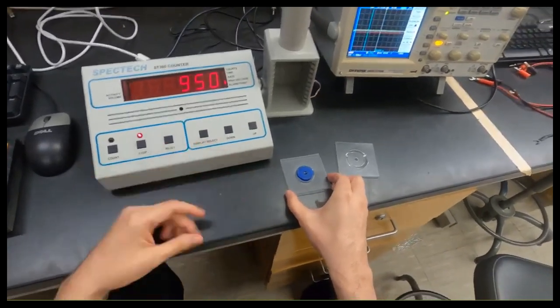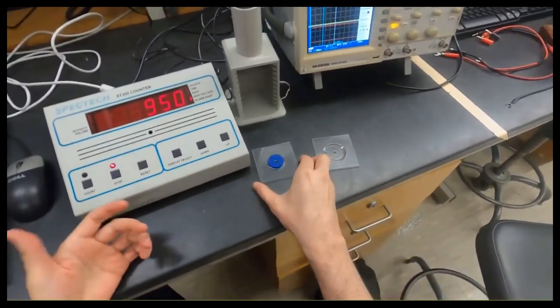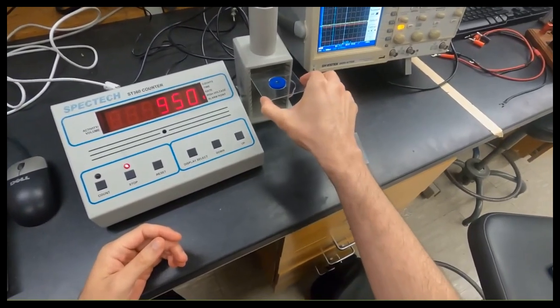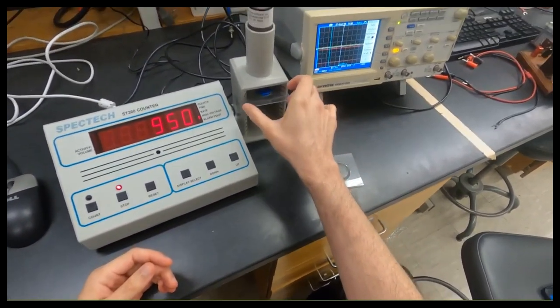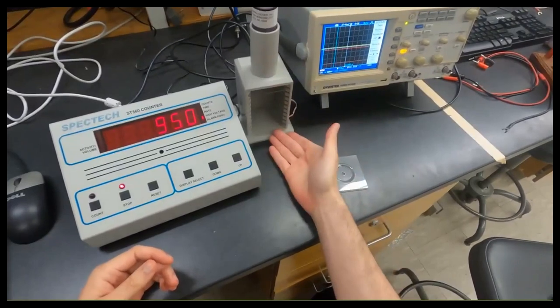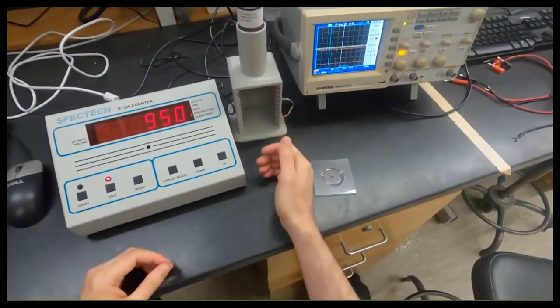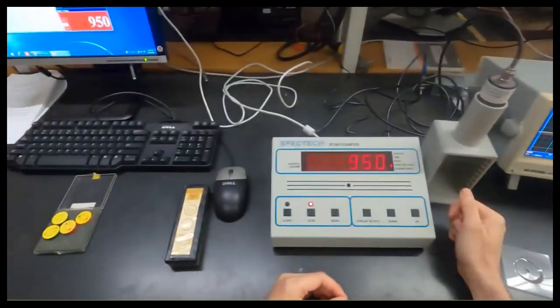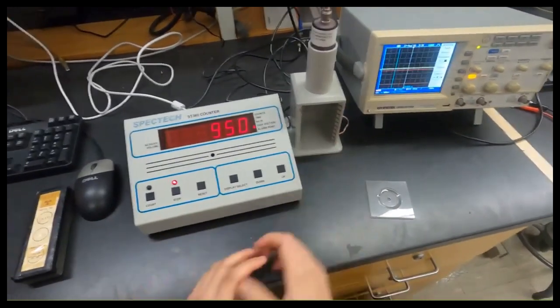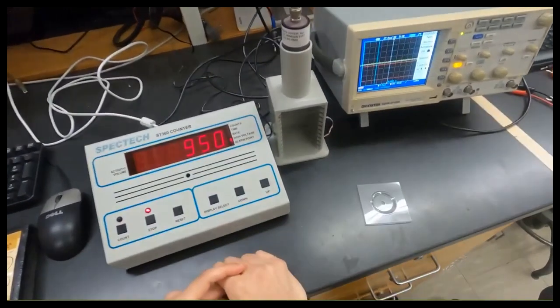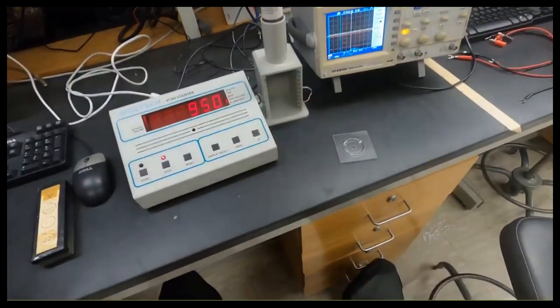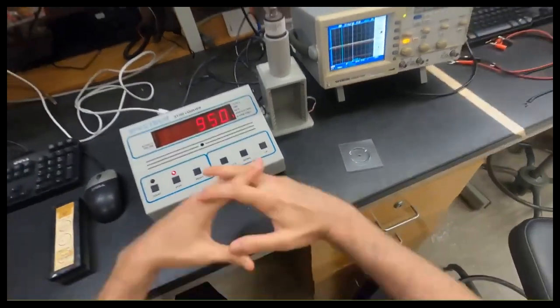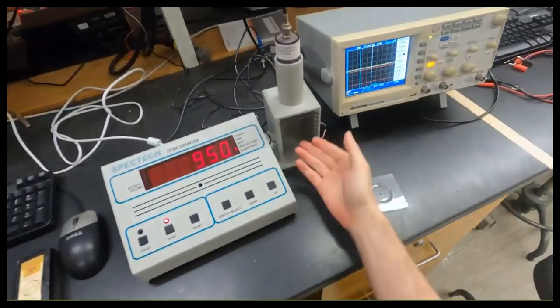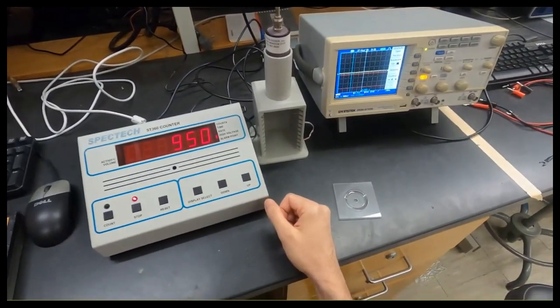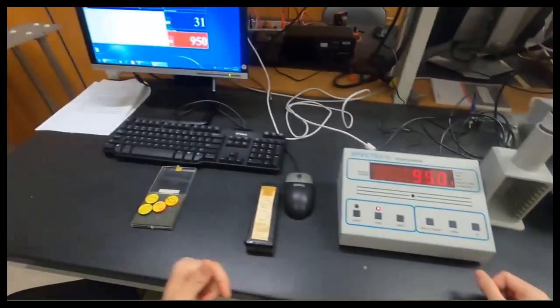And you know, sometimes people ask where to put it. I prefer to put it in the first one because then I get more counts. If I put it in another place here, I'll get fewer counts because the sample emits radioactive particles in all directions, like it's a sphere. So if you are far away from your detector, you get fewer counts.